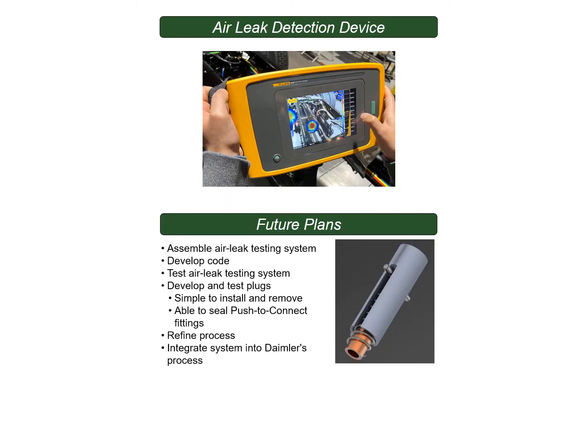We will be able to detect leaks using the Fluke II900, which picks up on ultrasonic frequency. This displays a visual on the screen which intensifies depending on the size of the leak.